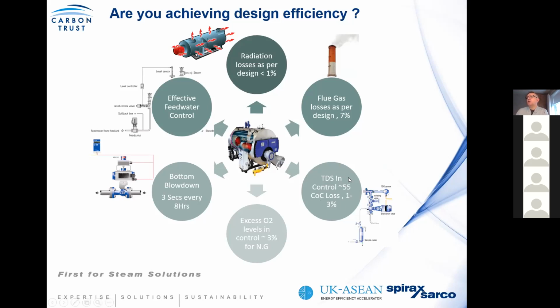However, we should be looking at your TDS control. Are you in control? Are you operating at cycles of concentration of maybe anywhere from 50 to 100? Because in an effective system, your TDS blowdown should be less than 1%. In reality, what we're finding can be up to 5% where there's ineffective control.